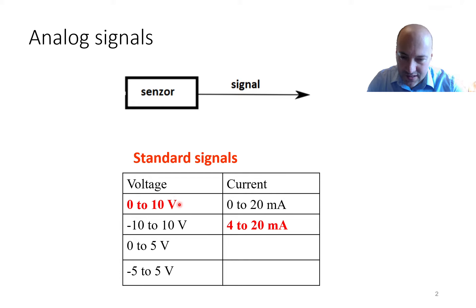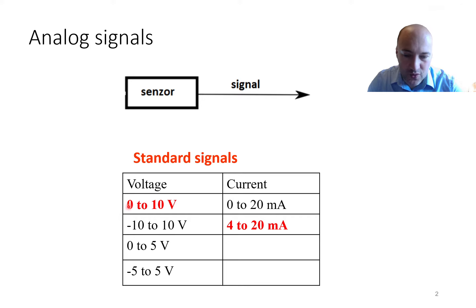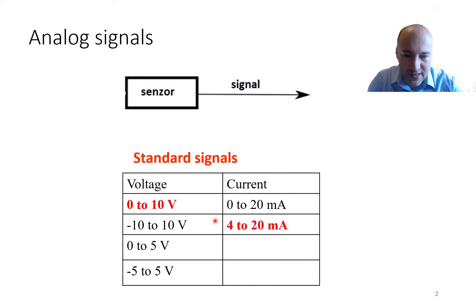What does this mean? If I measure a variable such as temperature, the minimal value of my variable corresponds to the minimal value of my range. For example, if I measure temperature between minus 50 and 100 degrees Celsius, then minus 50 corresponds to 0 volts and 100 degrees corresponds to 10 volts. For the current signal it is similar — the minimal value corresponds to 4 milliamps and the maximum to 20 milliamps. You can connect such a sensor to any control system such as a programmable controller.